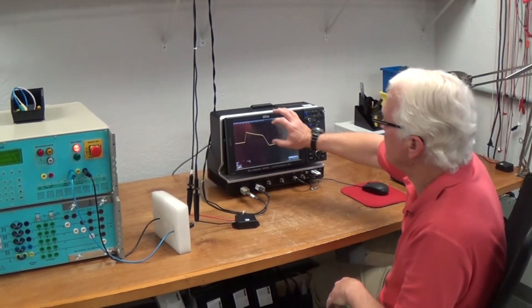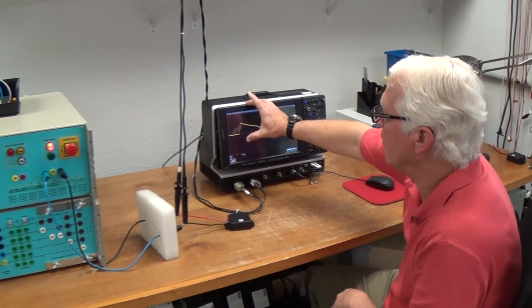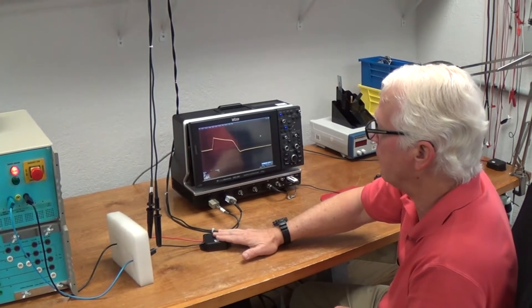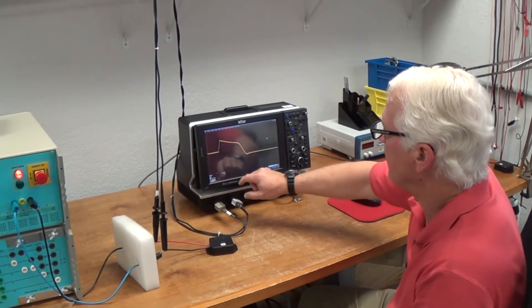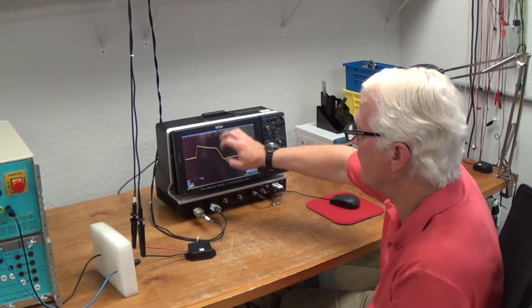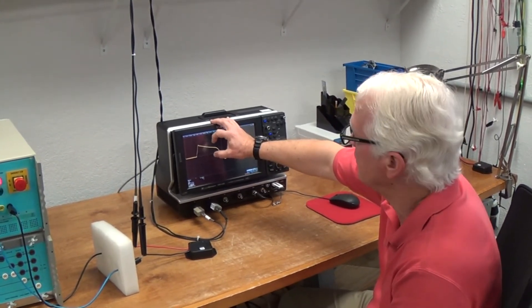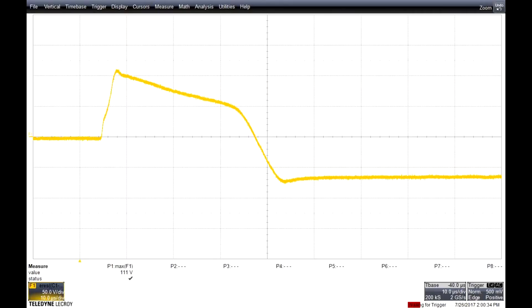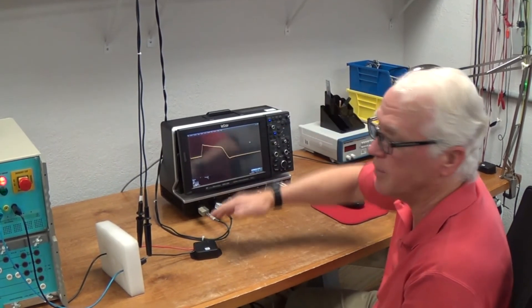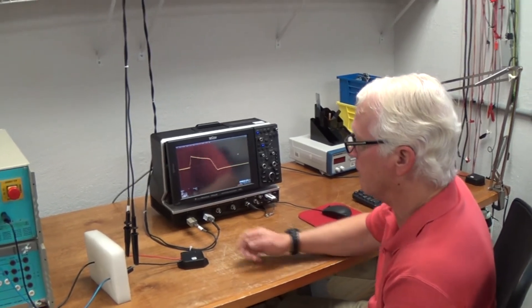Okay, again, this would go all the way to 1,000 volts if it weren't for the surge protector. Because of the surge protector, this has been cut off and the let-through voltage is 111 volts. So all that other voltage has been diverted by the surge protector and absorbed.